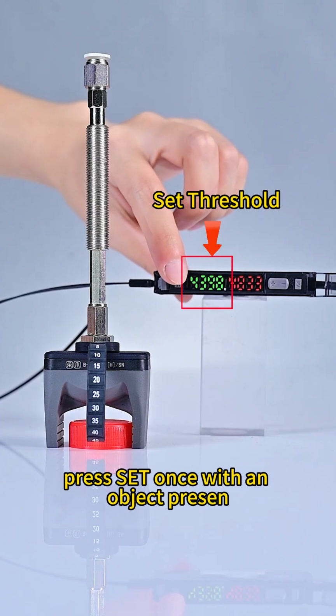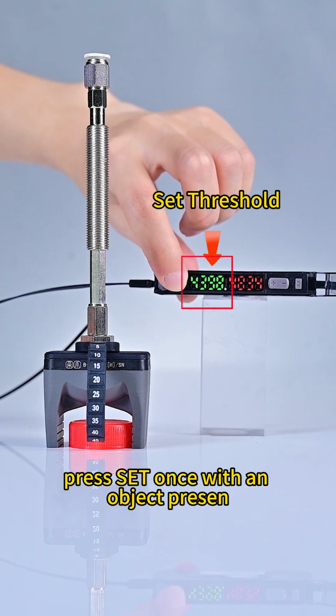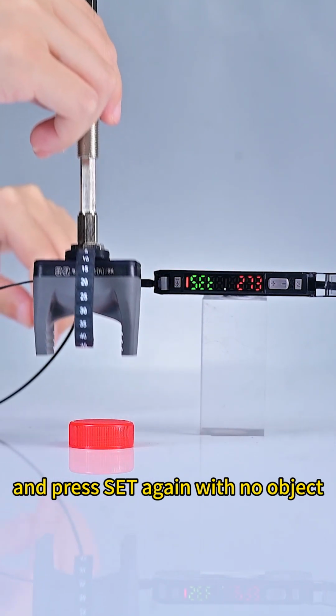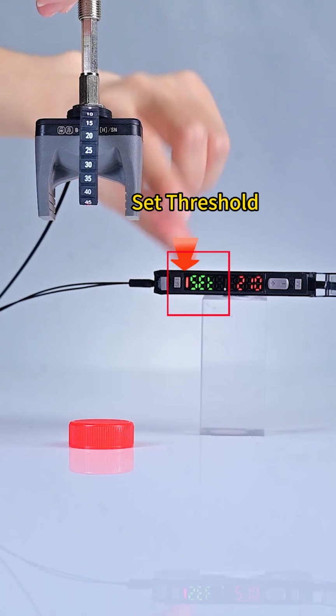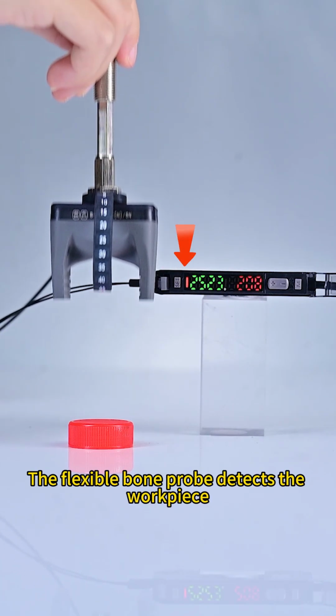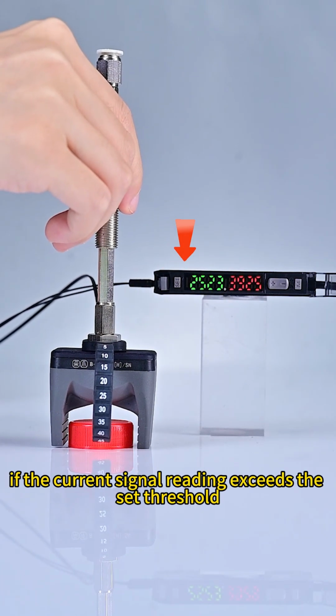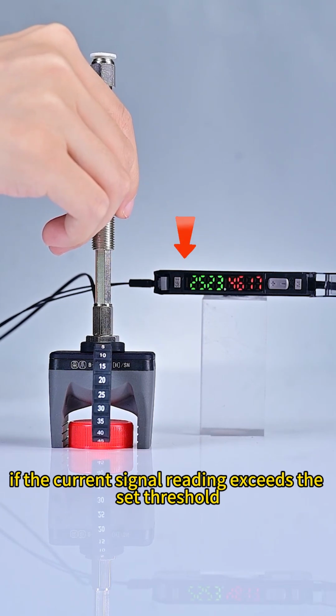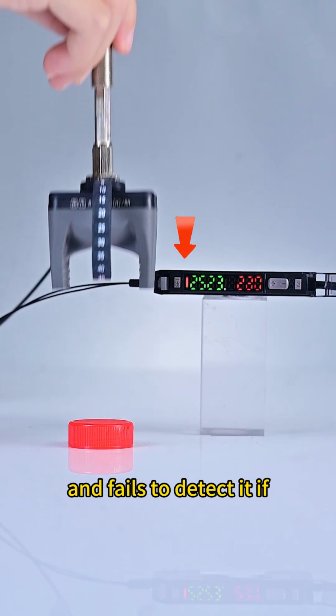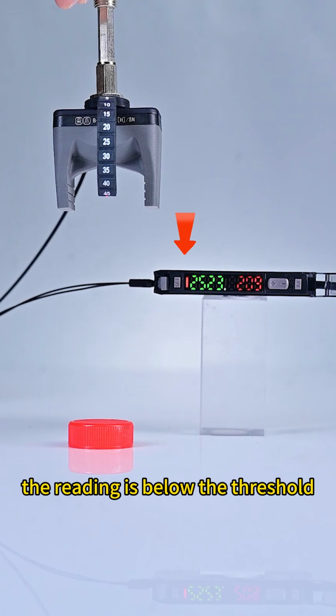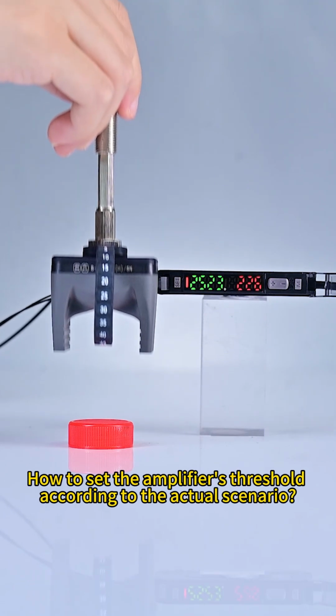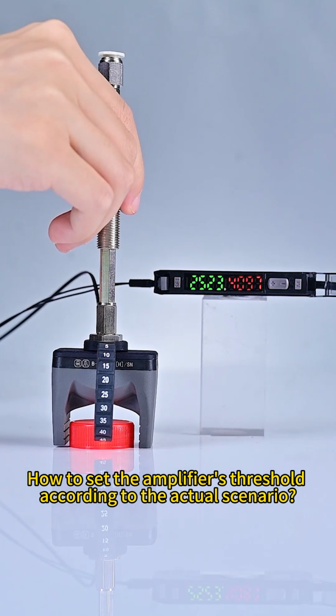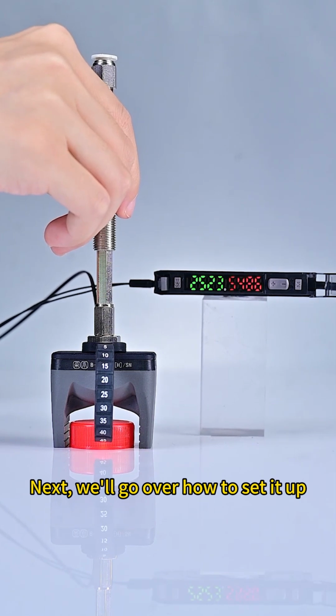Press SET once with an object present, and press SET again with no object. The flexible bone probe detects the workpiece if the current signal reading exceeds the set threshold, and fails to detect it if the reading is below the threshold. How to set the amplifier's threshold according to the actual scenario. Next, we'll go over how to set it up.